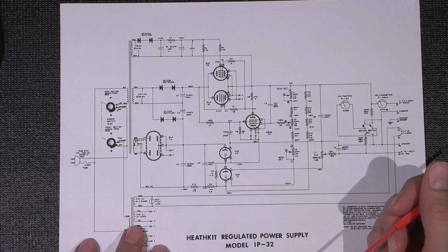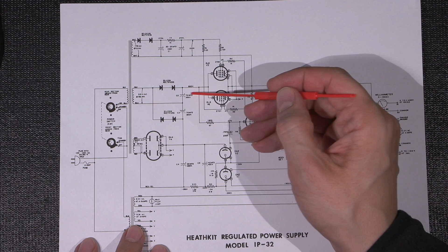In these power supplies, you'll see they're using 70 microfarad capacitors rated at 350 volts. It's very okay to use 100 microfarad, no problem at all. Chances are the reason they used 70 is because they had box loads of these things kicking around. It's always okay to increase the capacitance in a power supply a little bit - you always want to make sure you're above their rated voltage. This is 350, so in my case I'm going to install 450 volt caps.